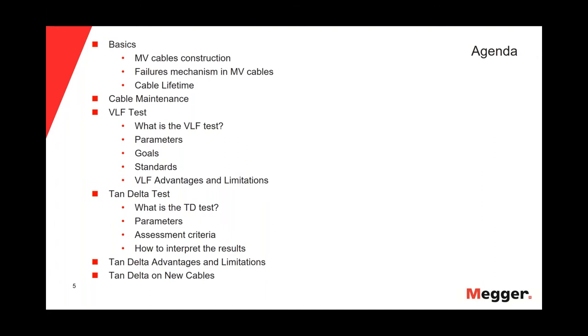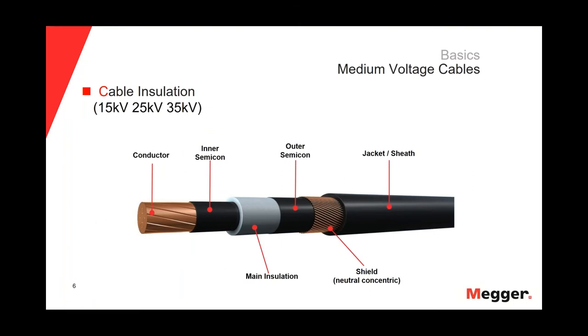Let's start with the basics of medium voltage cables. The single-phase cable shown in this slide is the classical construction for medium voltage cables, in which we have a center conductor that could be copper or aluminum. Next, we have the inner semi-conductor layer. Then we have the main insulation — in this case the cable shown is an XLPE insulation. Next, we have the outer semi-conductor layer, then the concentric or metallic shield of the cable, and finally the jacket.